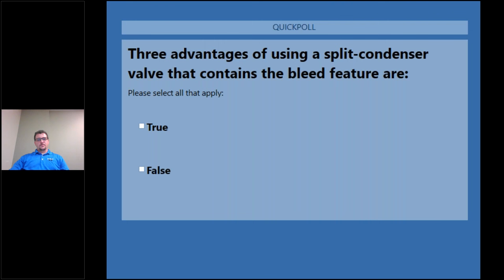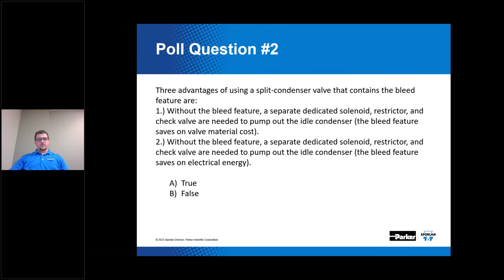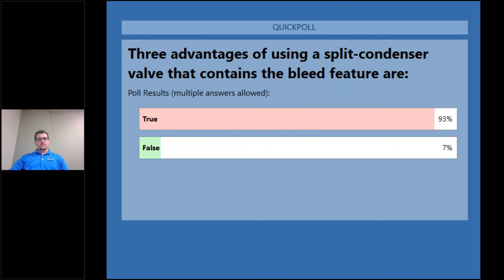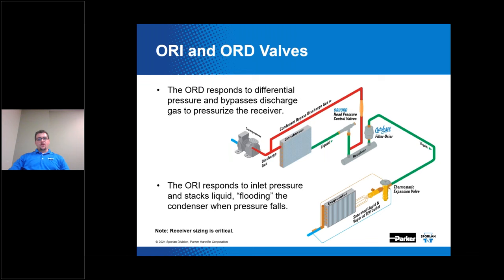The majority got this correct — 93 percent chose True, 7 percent chose False. The three advantages of using a split condenser valve with the bleed feature are: it eliminates the need for a separate solenoid, restrictor, and check valve, saving on valve material cost; it saves on electrical energy; and bleeding the idle condenser reduces the total refrigerant charge in the system.